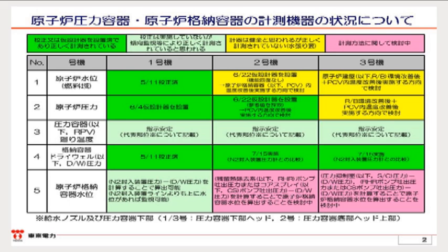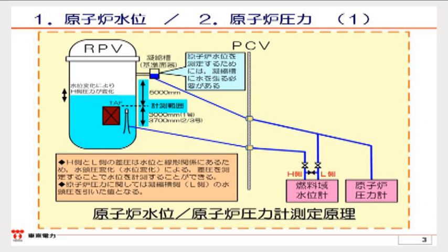Next, let me explain the water level of the reactors. Please look at the next page, slide number 3. As reported several times before, the water level of the reactors is measured as shown in this figure, in a way that the condensate pot is substantially filled with water and the level is the measurement criterion. If the water level varies, the pressure on side H printed in this water level gauge varies accordingly. With this variation and the hydraulic head pressure on side L, which is constant, we convert the difference of the two pressures into the water level. This is how we measure the water level.